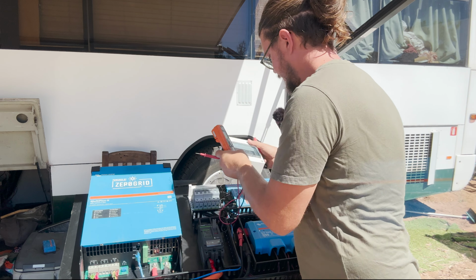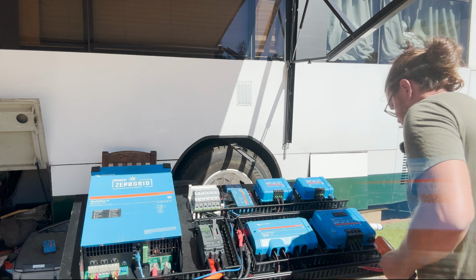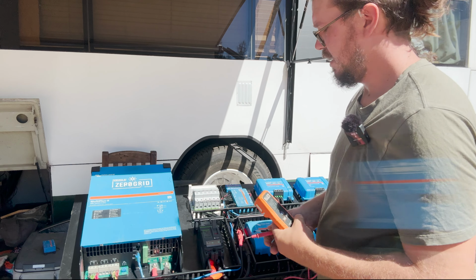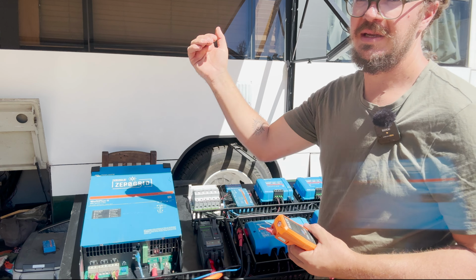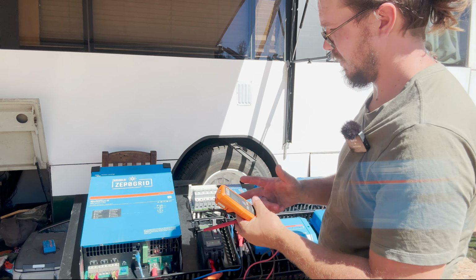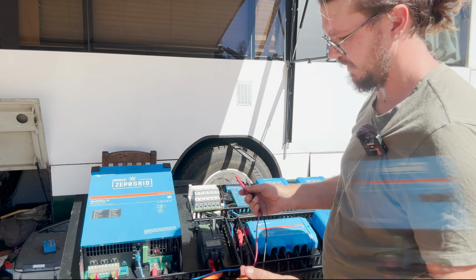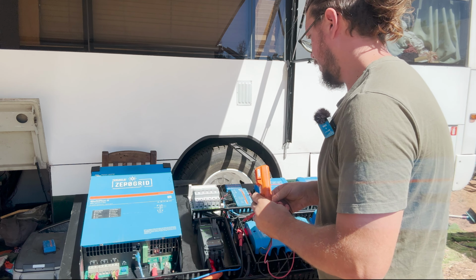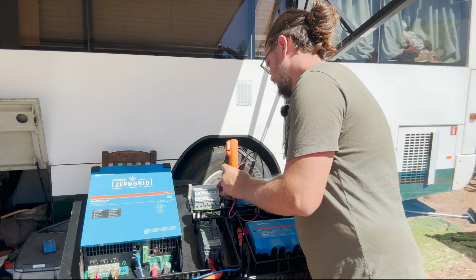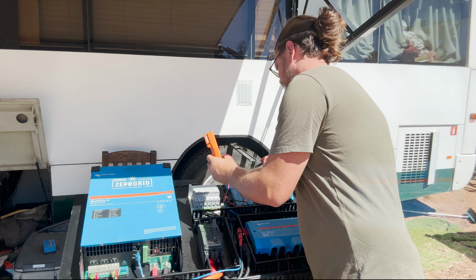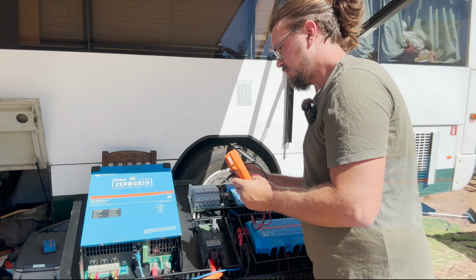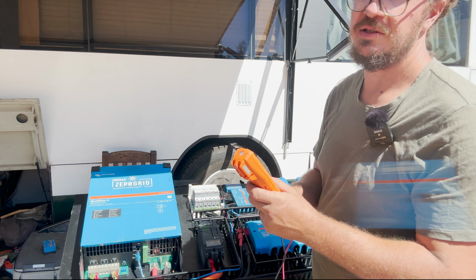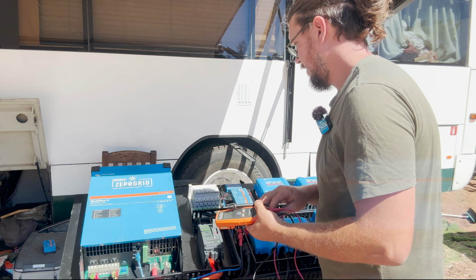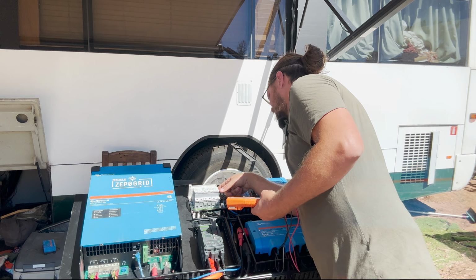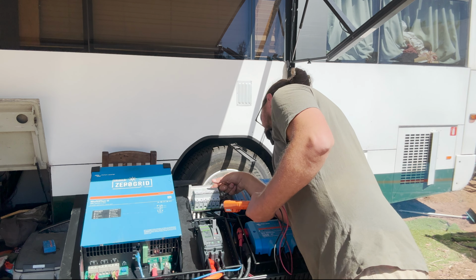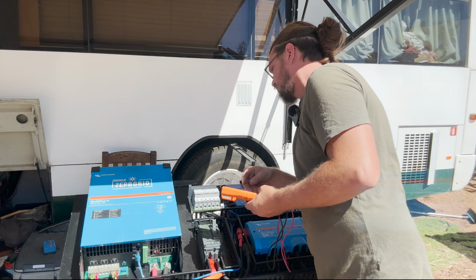So let's get into testing the MPPTs. These are the cables coming down from the roof - I'm going to have 3 strings, 2 from the roof, one from the back of the bus. With these breakers, it doesn't matter if they're on or off, but the cables I use are like a DC cable, and they do have a red line on them. So we can first do a visual inspection to make sure we've got one with a red line, one without, one with a red line, one without, one with a red line, one without.